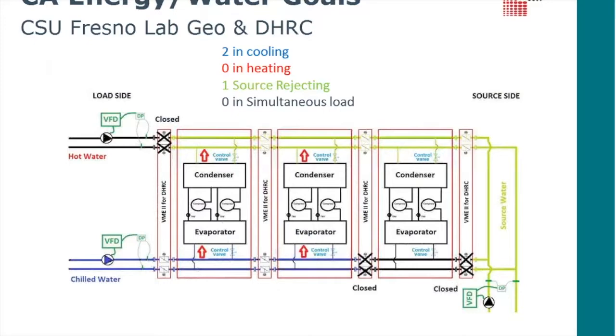If more cooling is needed, you turn on the second module, then the third. If you need heating, you start turning on the heating modules, and now you're doing heat recovery across your chilled and hot water loops, with a big energy benefit there. If by chance you had a similar load in heating and cooling, this chiller could do all the heating and cooling just by rejecting heat between the two loops. That's sort of an ideal situation, but the point is that it's a pretty energy-efficient device.